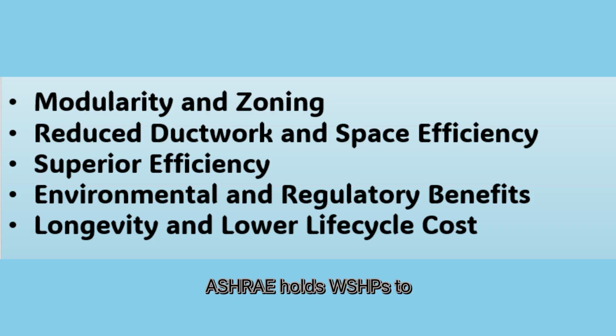D. High energy efficiency. ASHRAE holds WSHPs to stricter standards, 13.0 EER for cooling and 3.7 COP for heating, thanks to water's superior heat transfer. A 2,000-gallon loop between 50 and 90 degrees F can store over 650,000 BTUs, acting as an energy buffer.